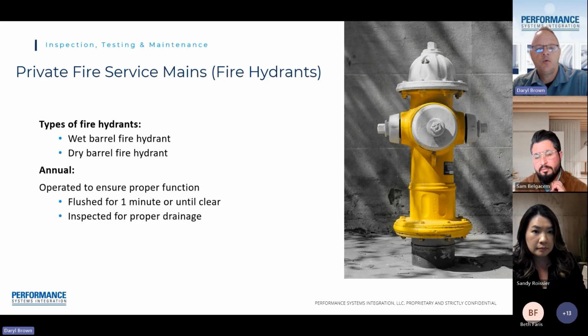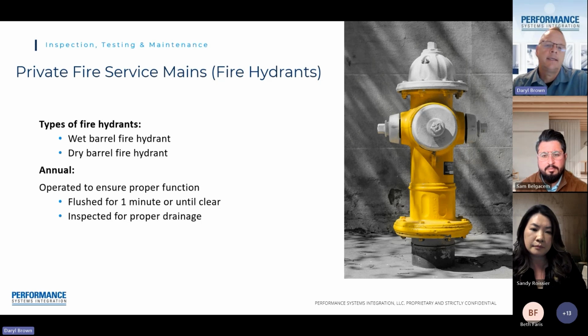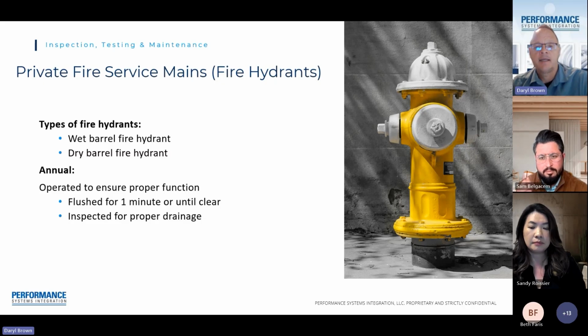These pertain to if you have a large-scale property that has on-site parking. Oftentimes, these on-site parking sites, because of their expansive nature, have additional fire hydrants located throughout. You'd have to check with your local jurisdiction, but most jurisdictions require that you actually maintain these hydrants yourself. And these are actually an annual requirement that we do flushing on these hydrants.